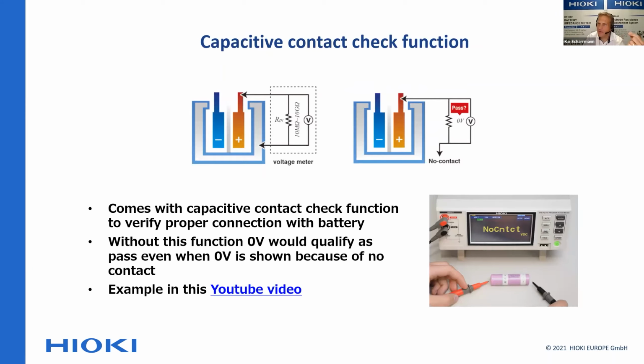The difference with our DVM is that there's a contact check function, a capacitive contact check function, which figures out whether you actually have contact to the DUT. If you don't have contact, the display or message will show there is no contact. That's the crucial element, and that's why you cannot use any random digital multimeter for these tests - you need an instrument with a contact check function.